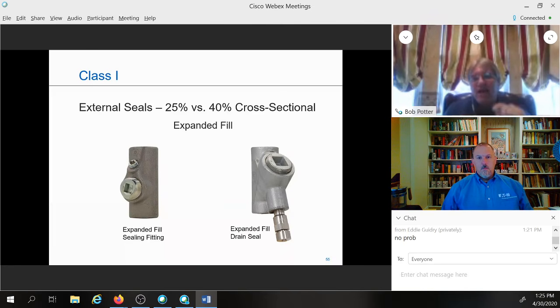Once I do that, the National Electrical Code will allow me to run that, for example, MC cable through my sealing fitting as if it was one conductor. Also, if I have those data type cables that are real tight and not capable of transmitting gases, when they're running in conduit, they can be run through as one single conductor. We also have a seminar that discusses cabling in hazardous location areas and touches on some of these subjects much deeper.